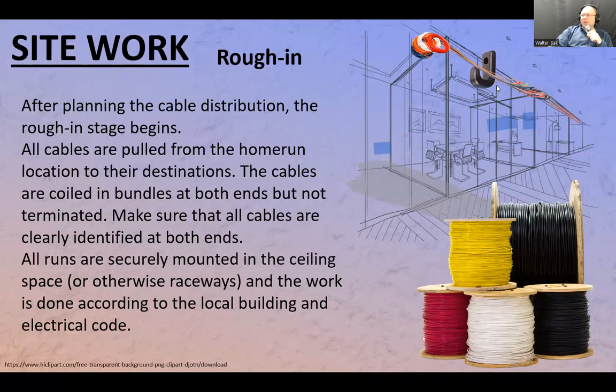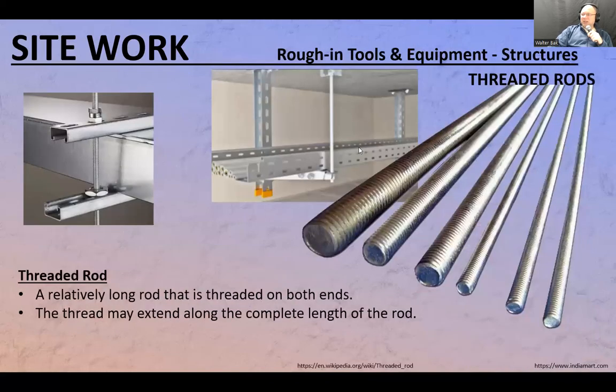So generally 4 feet apart gives you a nice compromise. You could do every 6 inches, no problem, but you're not going to do that because it's going to take forever and cost a lot more money. Wasted. So 4 feet gives you nicely established straight lines, and avoids physical stress on the cables resting on the J hooks.